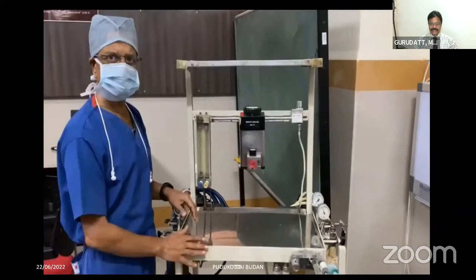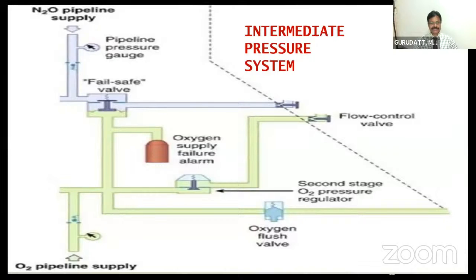Boyle's basic machine. The last part of the high pressure system was the pressure regulators. I have just completed the high pressure system. Let us move on to the intermediate pressure system. In the intermediate pressure system, we have the pipeline connections. You can see here the oxygen pipeline connection and also the nitrous oxide pipeline connection.